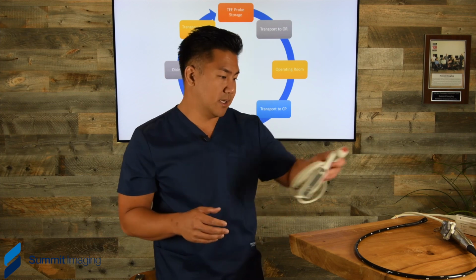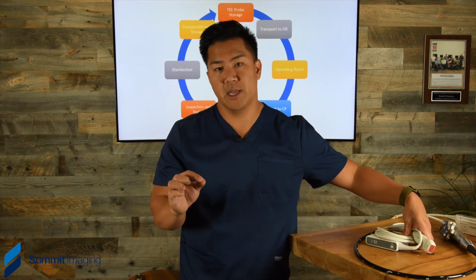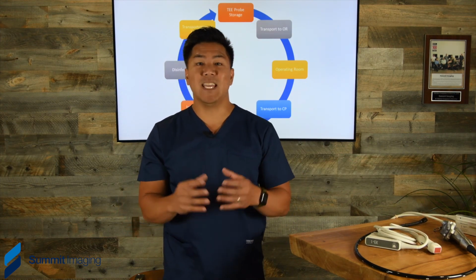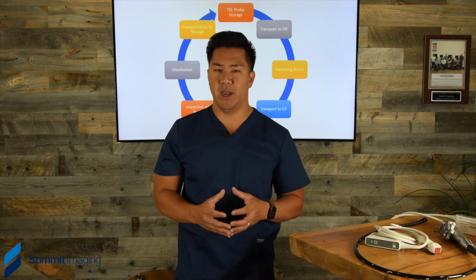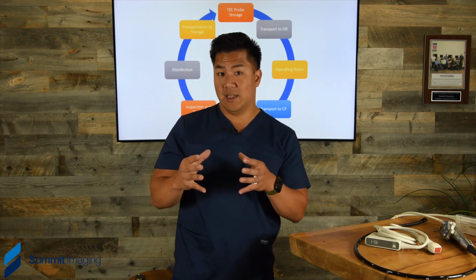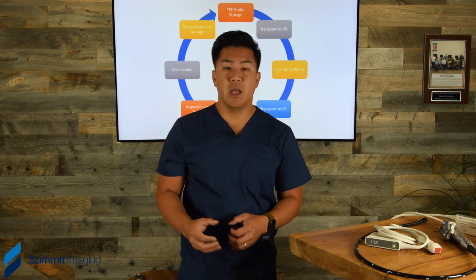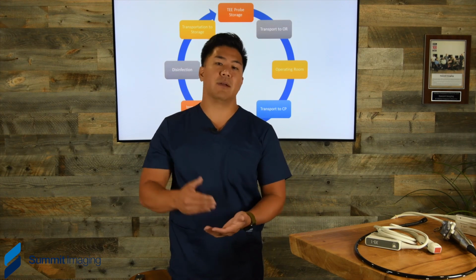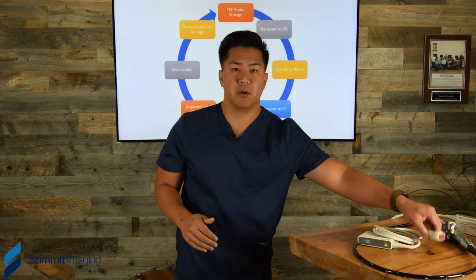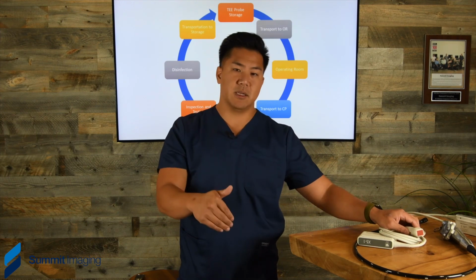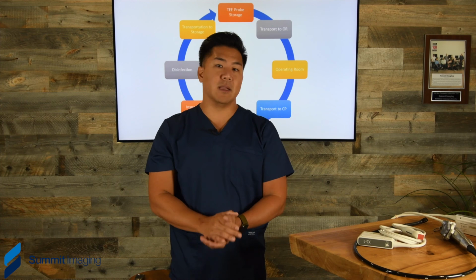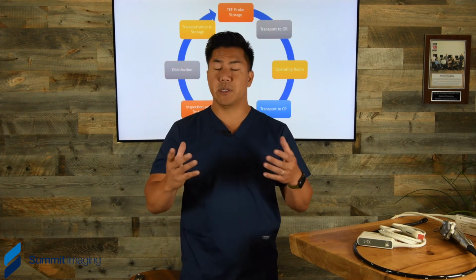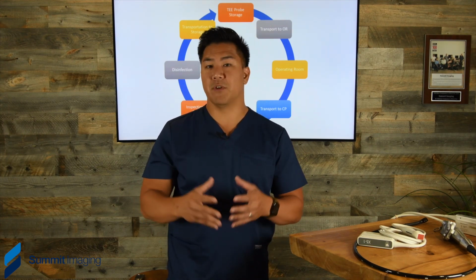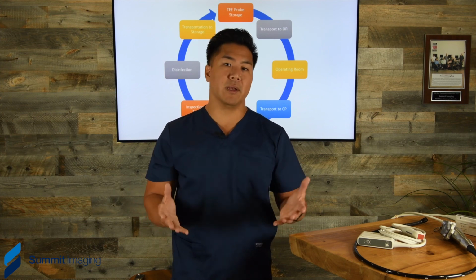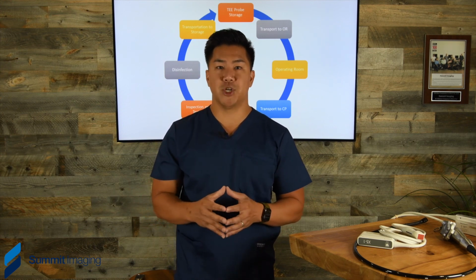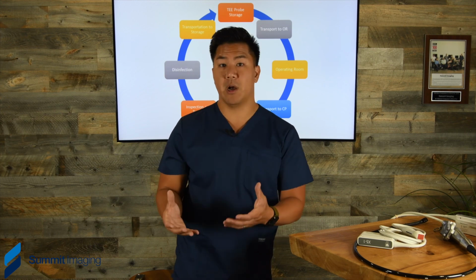And something as simple as a very small cut in the lens could be easily and very quickly repaired. And if it is not resolved immediately, the vulnerability is that now you've got fluid intrusion from the ultrasound gel of your transducer getting into the electronics underneath that lens and then causing corrosion. And if the corrosion sits there for too long, you're going to suffer image quality issues, and then at a point there's no materials left to repair, and therefore forcing a costly replacement.